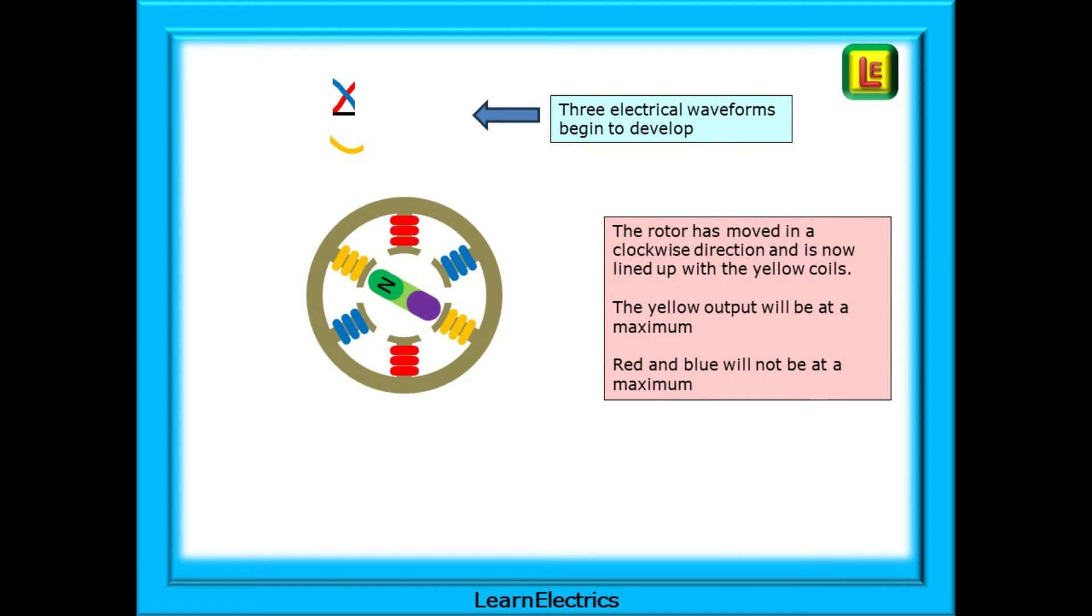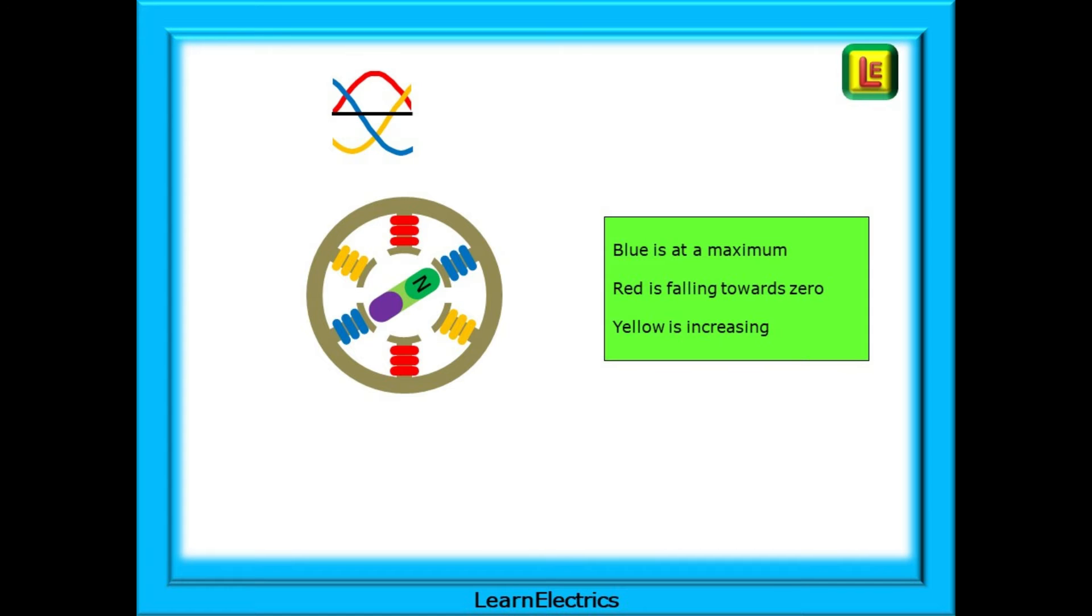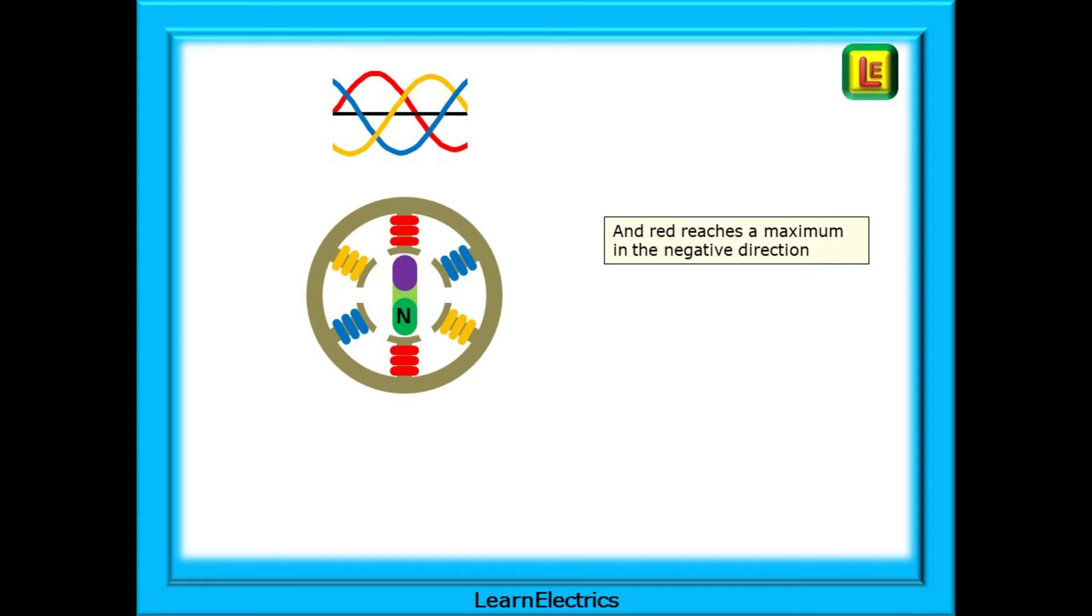The electrical waveforms begin to develop as the rotor rotates. The rotor has moved in a clockwise direction and is now lined up with the yellow coils. The yellow output will be at a maximum. Red and blue will not be at a maximum. Now the rotor is in line with the red coil. The magnetic flux is cutting across the red coils by its maximum amount. With maximum flux, we will have maximum voltage. But blue and yellow are not at a maximum. At this stage, blue is at a maximum. Red is falling towards zero and yellow is increasing. Yellow reaches its maximum voltage as the rotor lines up with the coils. Blue and red are at some midpoint voltage. More rotation and red reaches a maximum in the negative direction.